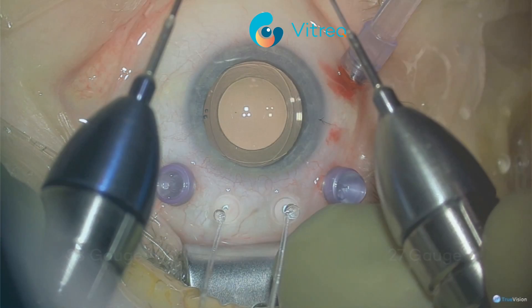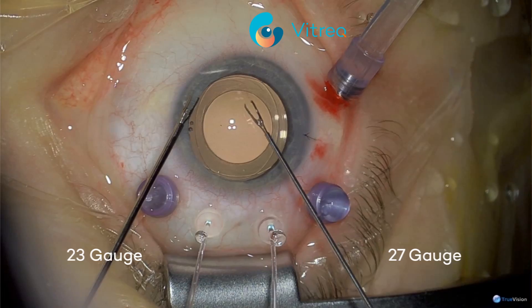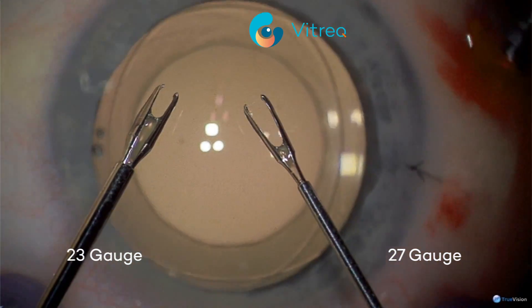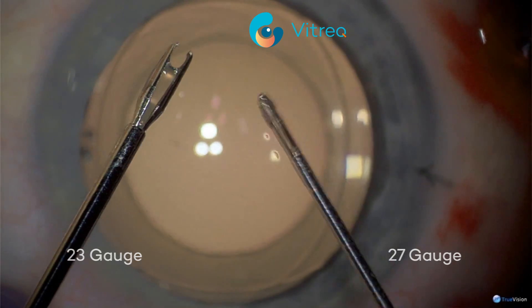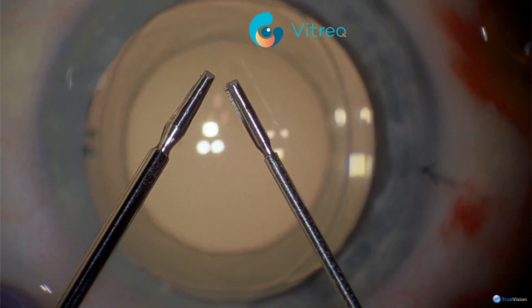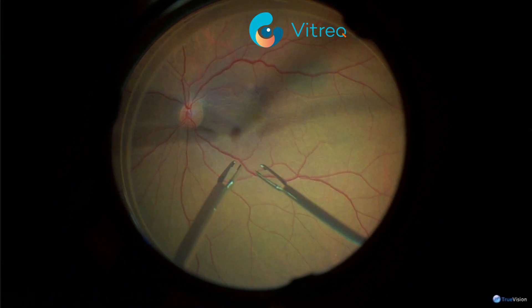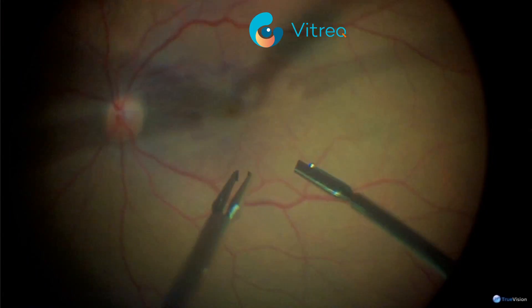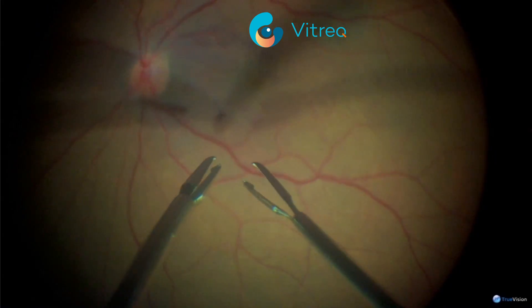Let's look at the surgical use of the instrument — we are now going into the operation room. In the surgeon's left hand is the Vitreq 23-gauge Eckardt forceps, and in his right, the 27-gauge version. As you can see, the tip dimensions are the same, except for the shaft diameter. Here is the intraocular view of the 23- and 27-gauge Eckardt forceps — no difference can be seen between the gauges.